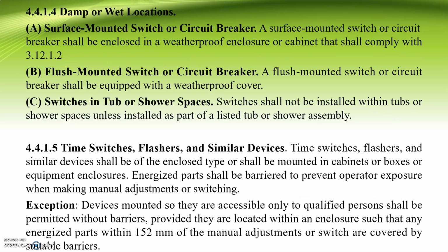So for chapter 4.4.1.4, damp or wet locations. So A, surface mounted switch or circuit breaker. A surface mounted switch or circuit breaker shall be enclosed in a weatherproof enclosure or cabinet that shall comply with chapter 3.12.1.2. So B, flush mounted switch or circuit breaker. A flush mounted switch or circuit breaker shall be equipped with a weatherproof cover. So letter C, switches in tub or shower spaces. Switches shall not be installed within tubs or shower spaces unless installed as part of listed tub or shower assemblies.